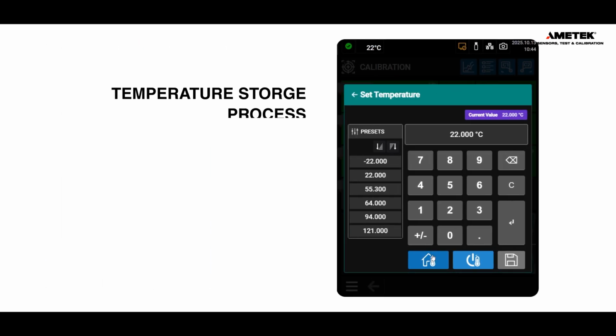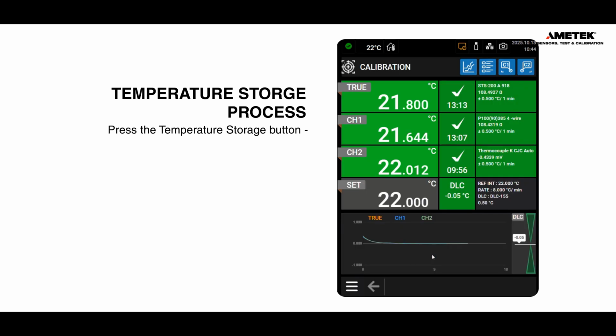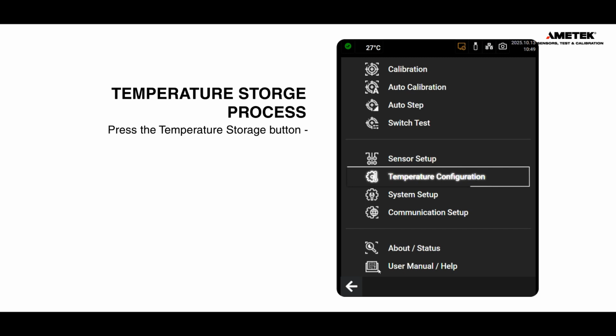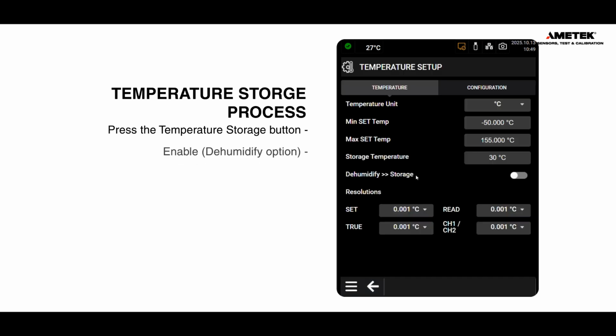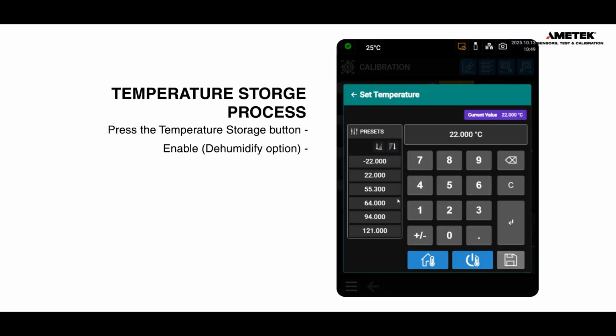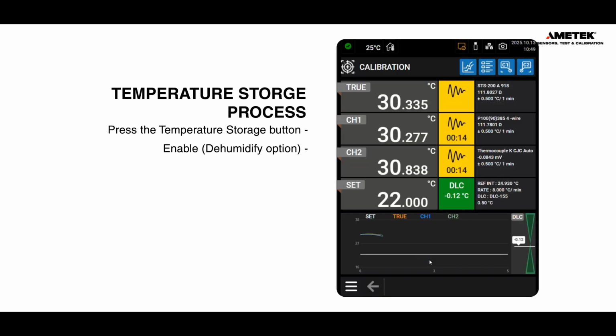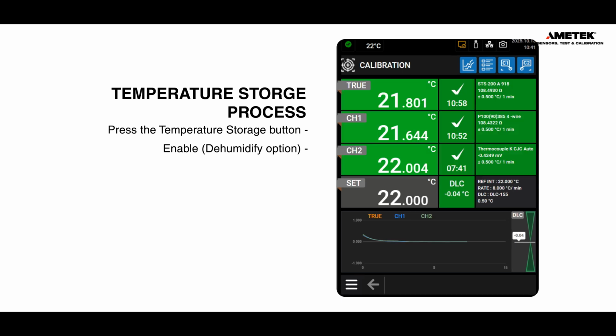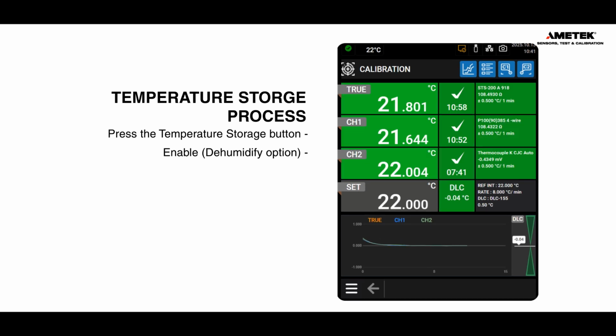To begin the storage process, press the Temperature Storage button. This activates the Prepare for Storage function. On the screen, you'll see the status of the Dehumidify option. If it's enabled, the calibrator will first heat up to 105 degrees Celsius to remove any moisture. Once that's done, it will automatically cool down to the storage temperature you've set.